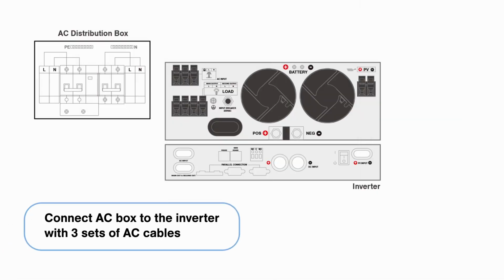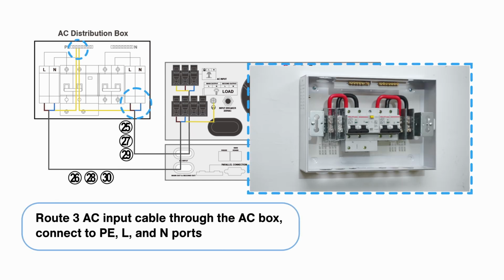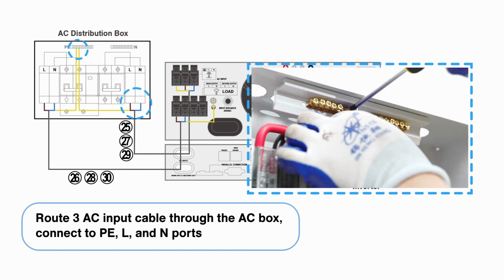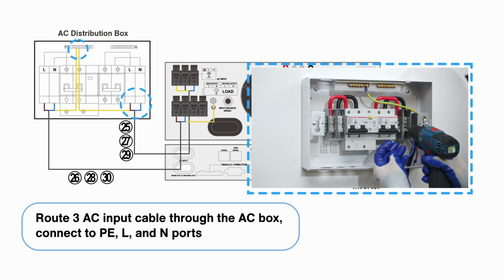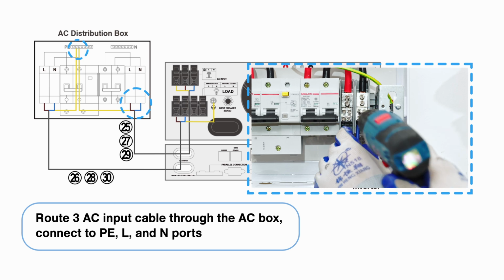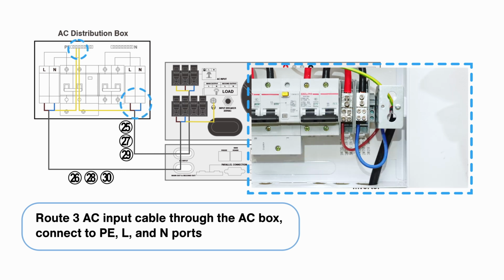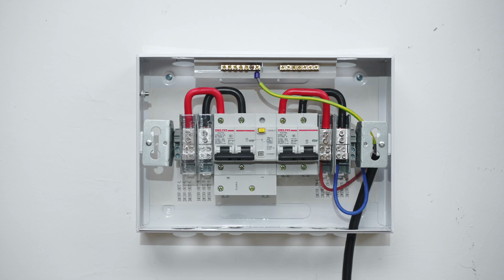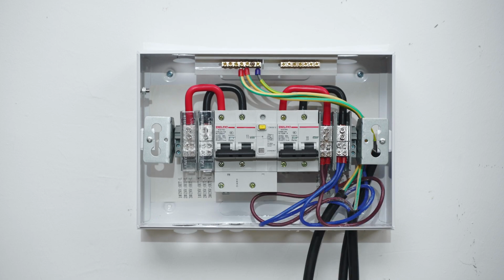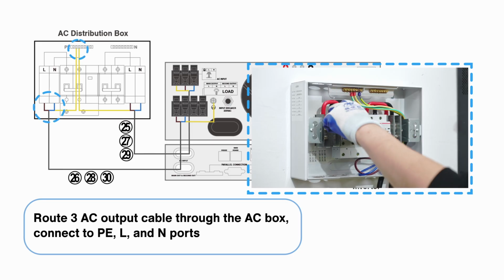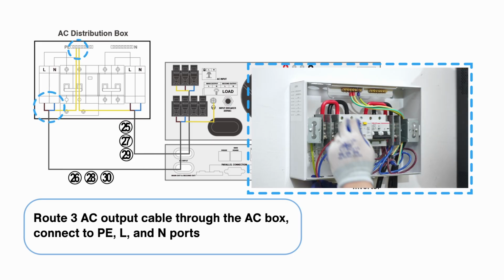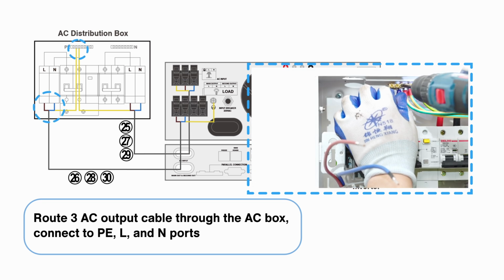AC line connection. Connect AC box to the inverter with 3 sets of AC cables. Route 3 AC input cable through the AC box. Connect to PE, L, and N ports. Route 3 AC output cable through the AC box. Connect to PE, L, and N ports.